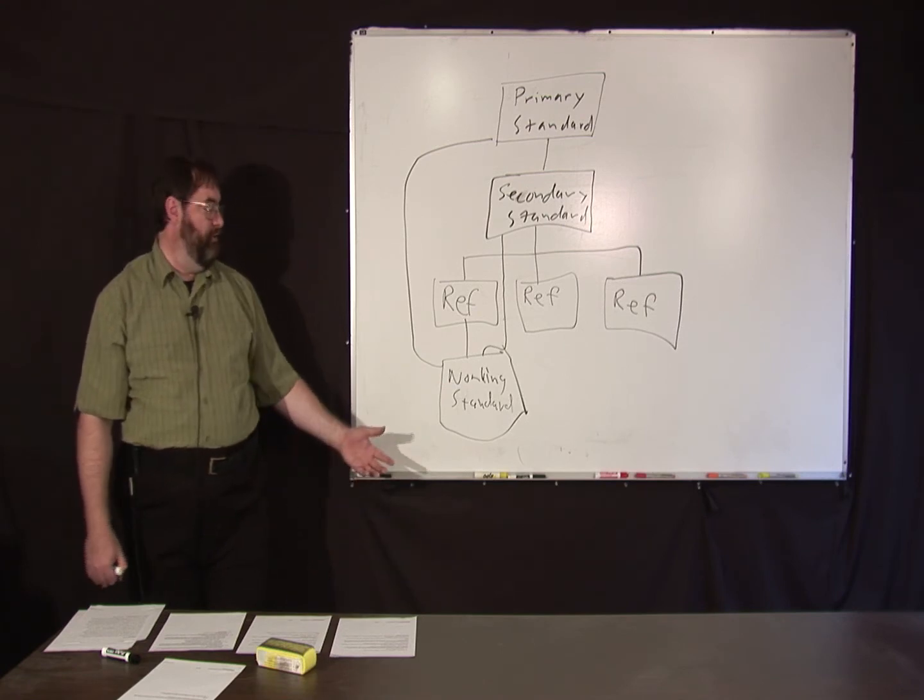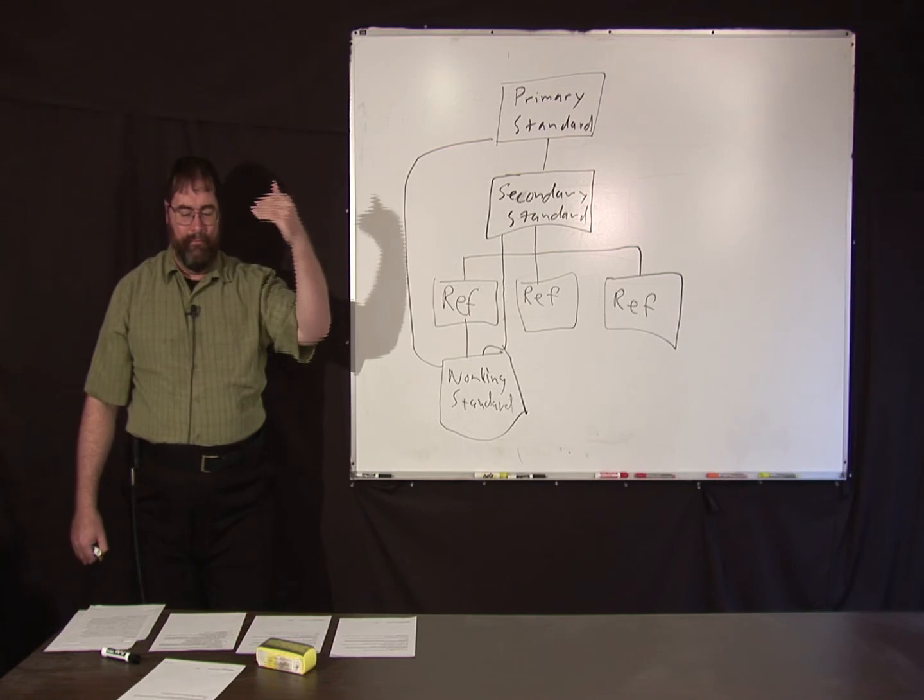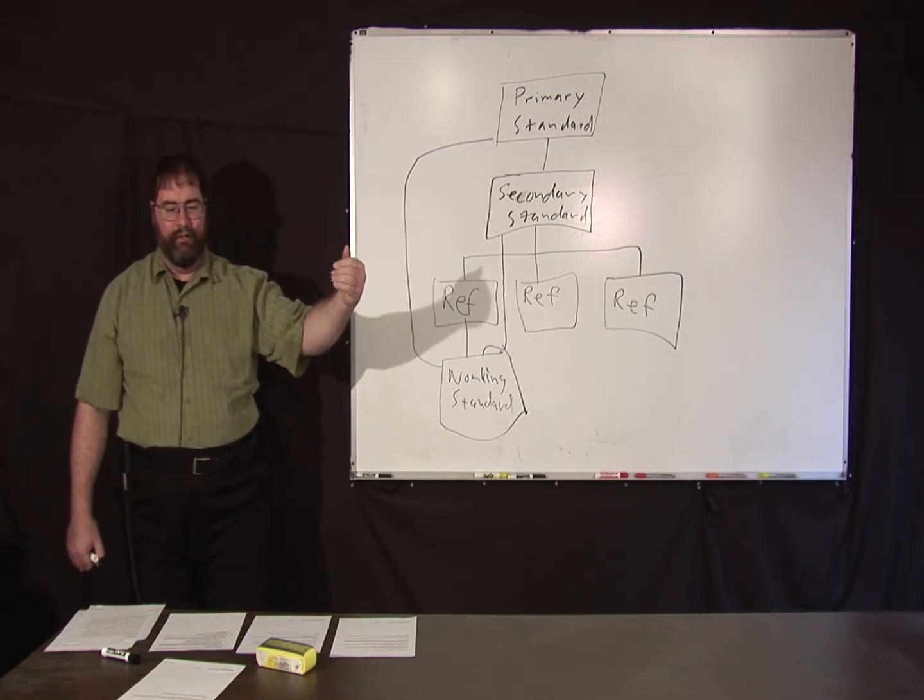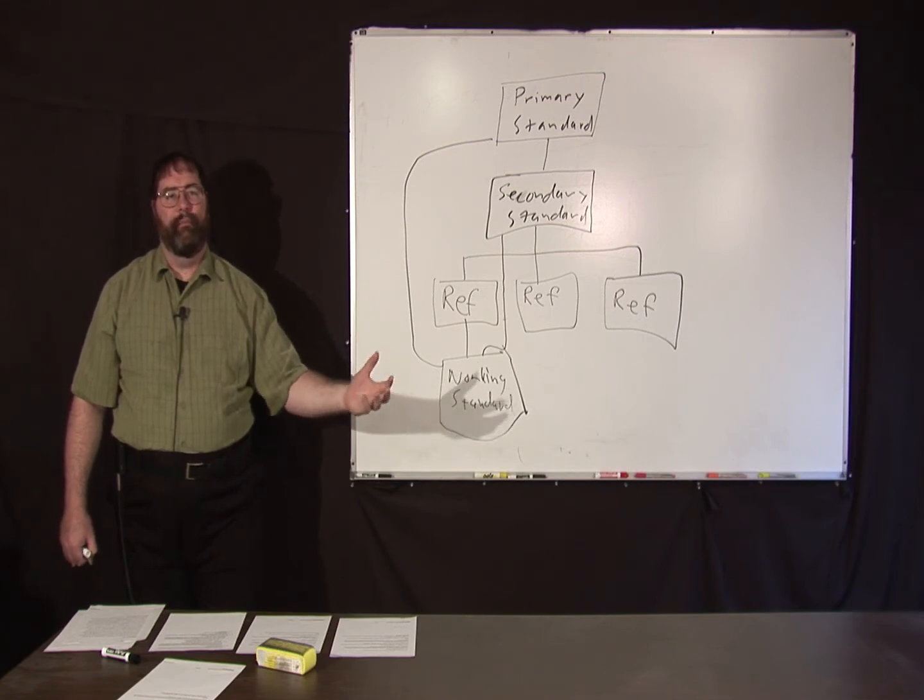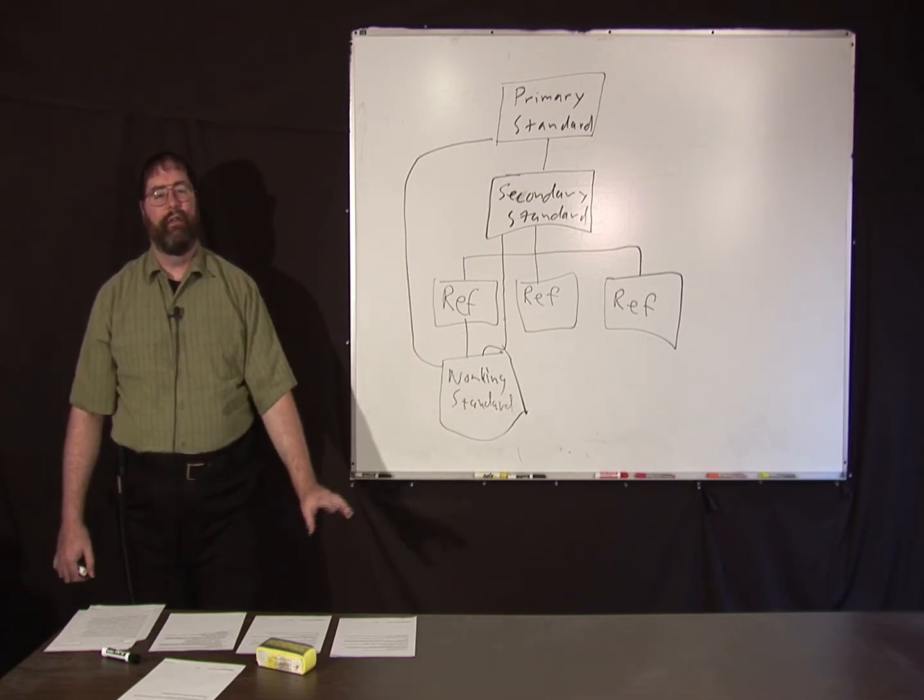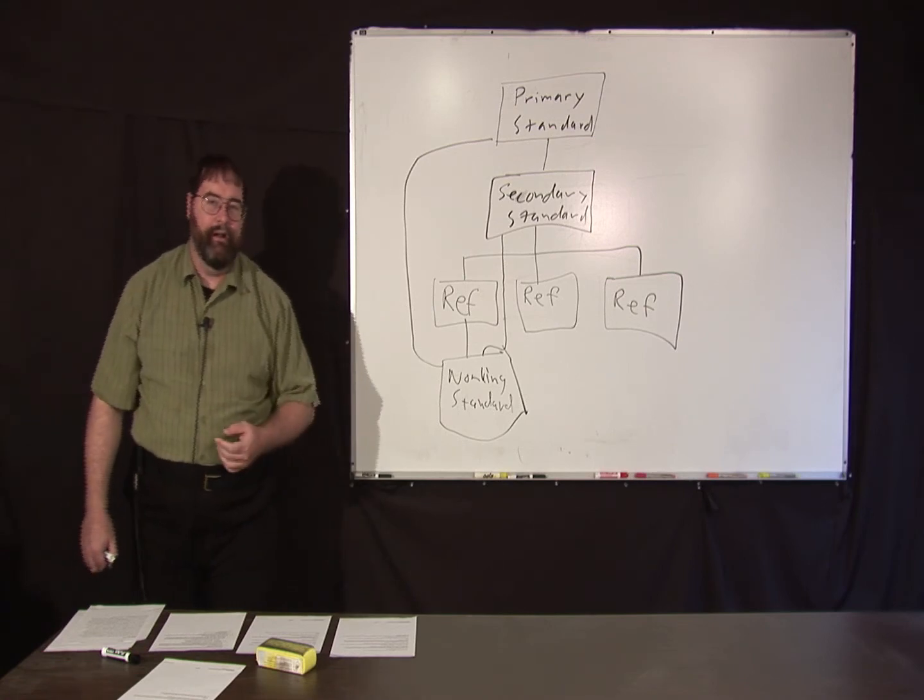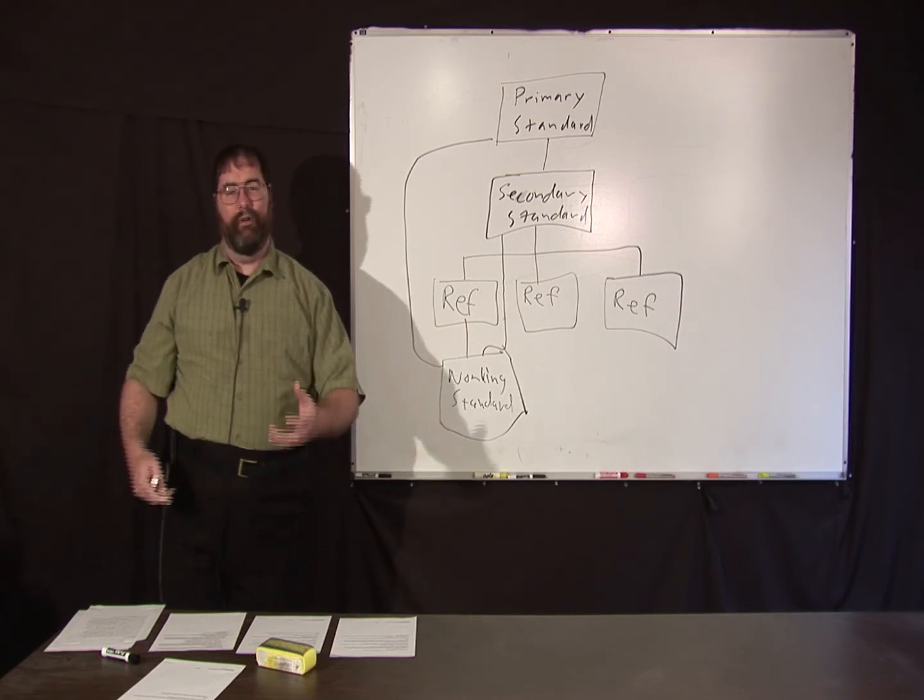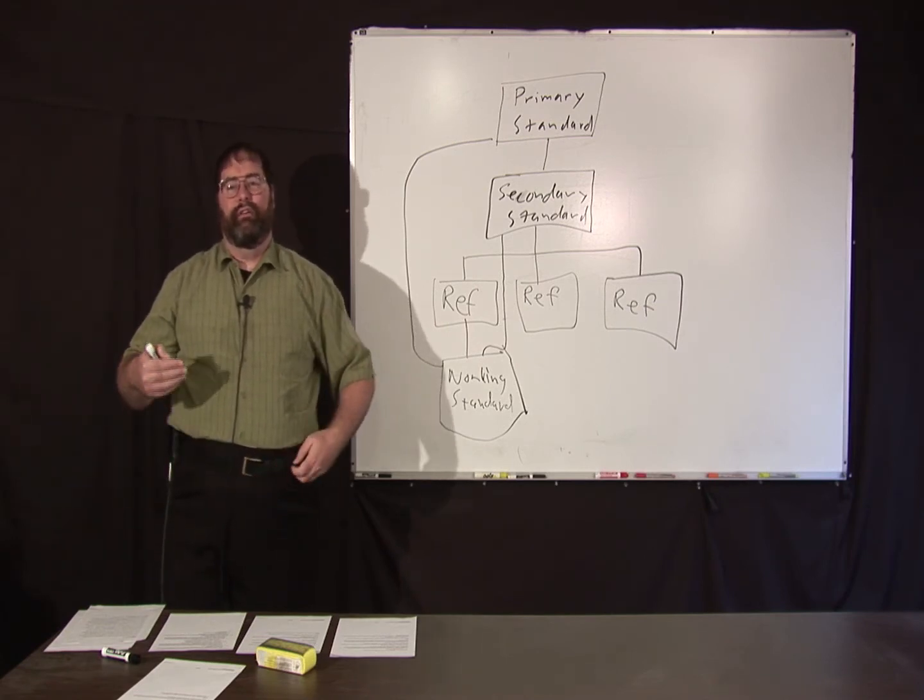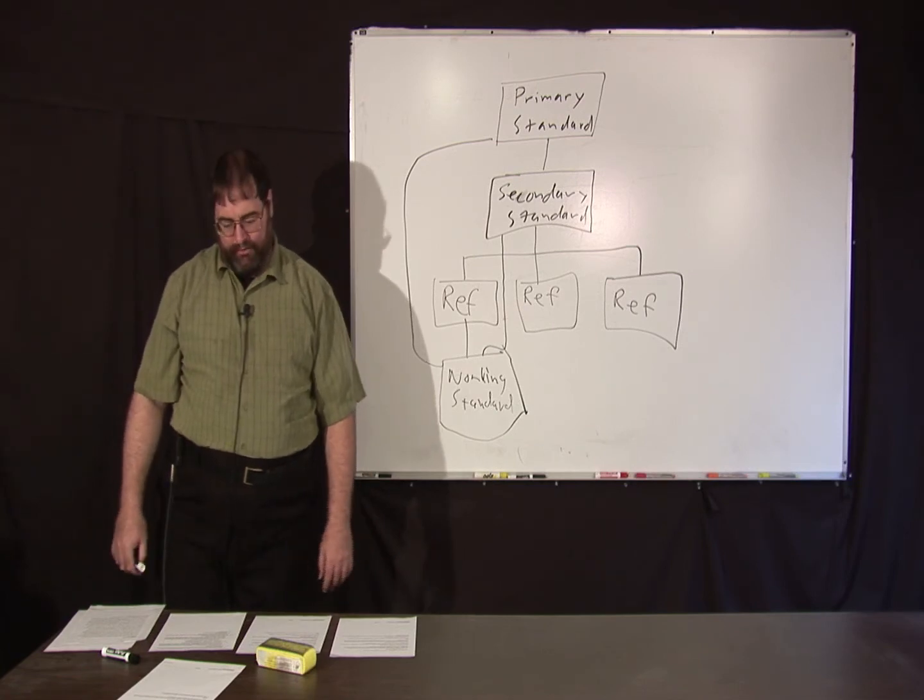So, for instance, your bathroom scale. You start out with the BIPM, national standards, go down to standards calibrated at a company. Finally, some sort of process at the end is used to check the calibration of the bathroom scale you buy at the store. So, that would be a traceable measurement, if you had the documentation, to prove that at each step of the way there was an unbroken chain of intercomparisons.